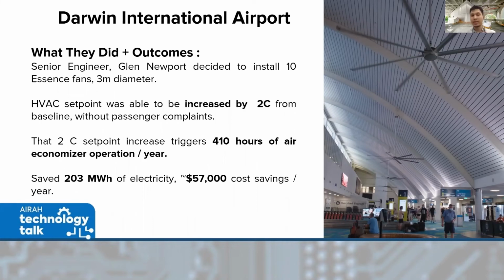So what they did, and the outcomes: the senior engineer decided to install 10 of our Essence fans, 3 meter diameter. Because of the increased convection cooling, they can increase the set point by 2 degrees without any passengers complaining. So it's good on them. And that 2 degree set point is actually enough to trigger their air economizer system as well, giving 410 hours of air economizer operation per year. Because of that, they saved 203 megawatt hours of electricity, or about $57,000 in cost savings per year. So they're very happy with the solution.